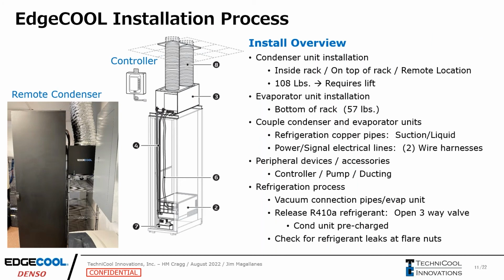So how is the unit installed physically? The condenser unit, like I mentioned before, is installed inside the rack, on top of the rack, or remotely. And this picture shows it installed remotely. This customer had really low ceilings. They just had enough clearance for the rack itself, so they put it right next to the rack. The condenser unit weighs about 110 pounds, so it requires a lift to help you get up there. The evaporator unit weighs about 60 pounds. It slides right in the bottom through some rack mount kits.